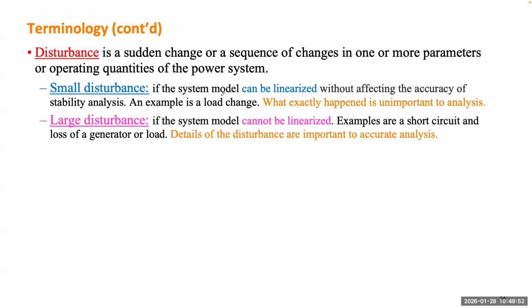But compared to a small disturbance, a large disturbance means we have to know exactly what happened, whether it's a line trip or a generator trip, and the location, because we need to simulate this disturbance in our system model. And if the system model is nonlinear, we cannot linearize, because all the details of the disturbance may determine the final response of the system. Examples are a short circuit fault, or a loss of a generator or load.